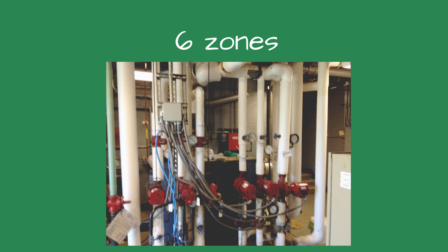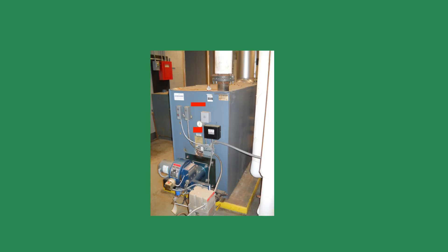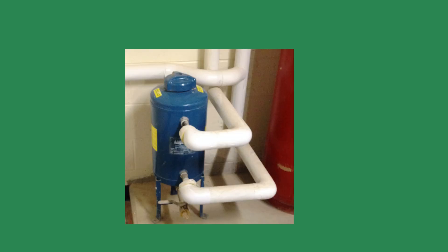The contact continued: whatever you do, we don't want another of these boilers. The boiler was a rugged boiler with a typical lifespan of 30 to 40 years — what caused it to start leaking after only five years? The hydronic loop had water treatment and a water meter on the makeup line. Checking the service reports, I saw the system only recently started losing water. Before that, it was a tight system with little water lost.